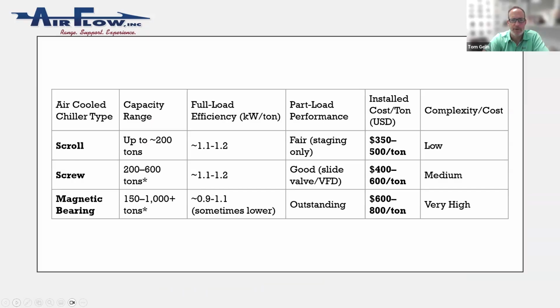For air-cooled specifically, thank you ChatGPT, this is roughly what's available. Our scroll chiller line from Dunham goes from 10 tons up to 180 tons. I think the market goes a little higher, maybe 220 or 230 tons for some scroll chillers. Those are the packaged round barrel type compressors, and they're the least expensive. They have less staging opportunity, they're simple, and they cost the least.